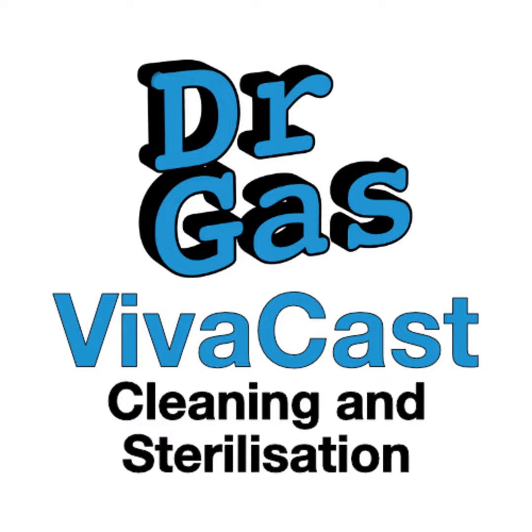And non-critical equipment contacts intact skin or is just present in clinical areas and can be cleaned again to a less high degree. Now, the levels are divided up into sterilisation at one end of the spectrum, disinfection in the middle, and cleaning. Cleaning is a fairly common sense definition, really. It's usually using soap or surfactants to remove contaminants from the outside of an object. That can include blood, feces, and things like that. Disinfection involves bringing microorganisms down to a safer level, but not necessarily destroying them all, and not normally including bacterial spores, such as Clostridia, for instance. So the critical equipment that's going to enter parts of the body that are normally sterile has to be sterilised. Now, sterilised meaning all living organisms are killed on that object so as to prevent cross-infection.